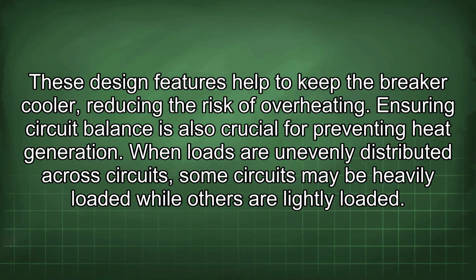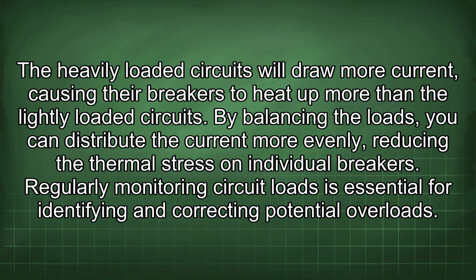Ensuring circuit balance is also crucial for preventing heat generation. When loads are unevenly distributed across circuits, some circuits may be heavily loaded while others are lightly loaded. The heavily loaded circuits will draw more current, causing the breakers to heat up more than the lightly loaded circuits. By balancing the loads, you can distribute the current more evenly, reducing the thermal stress on individual breakers.